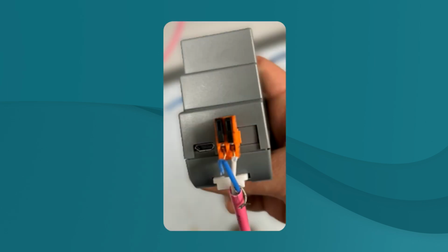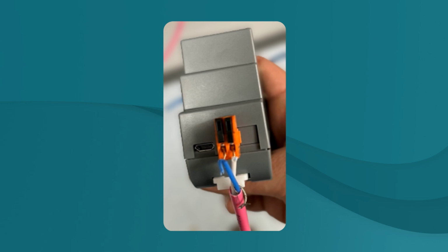To connect the Edge Supervisor to an AirStage VRF system, attach the pink wire to the network adapter. Attach the blue and white wires to the orange terminals. The silver, unshielded wire is not used. It does not matter which terminal each colored wire is attached to.